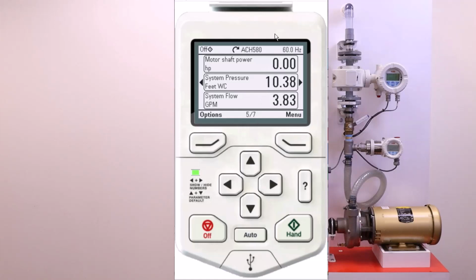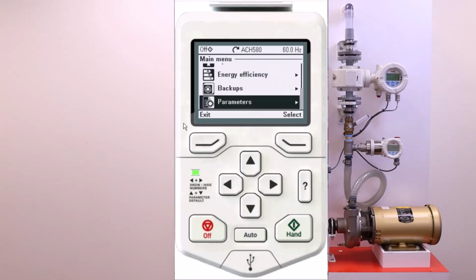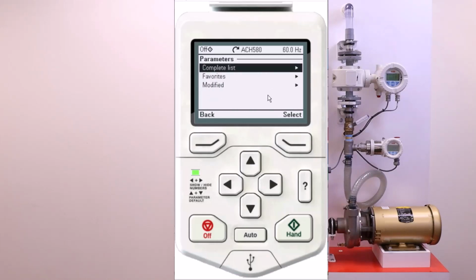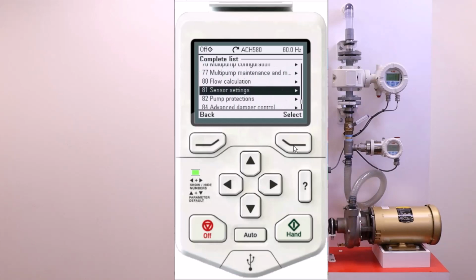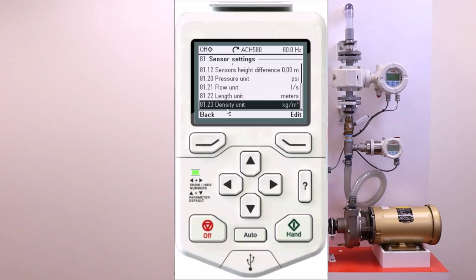I did some programming for the display, and I got the motor programmed all done. But let's look at putting in our data. So we'll go to menu. We're going to need to go to parameters, because we want to do sensorless pumping. So we'll go into parameters, and we'll look at the complete list. And the first group we're going to go to is our sensor settings. Group 81. We're going to go in Group 81 to set our units up. These are the units that are going to be used for sensorless pumping, and I want to set them to US units.